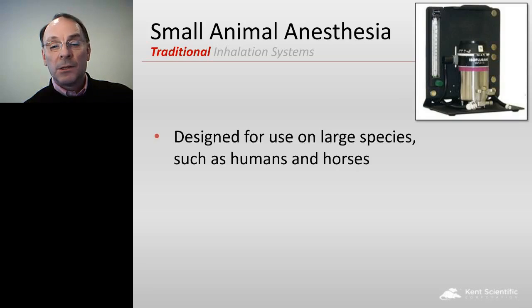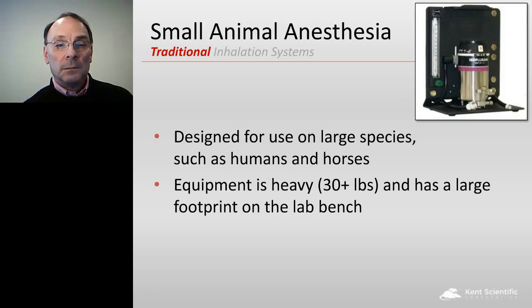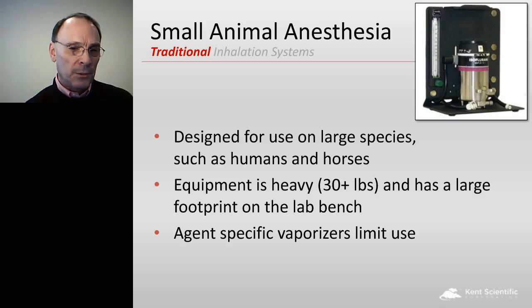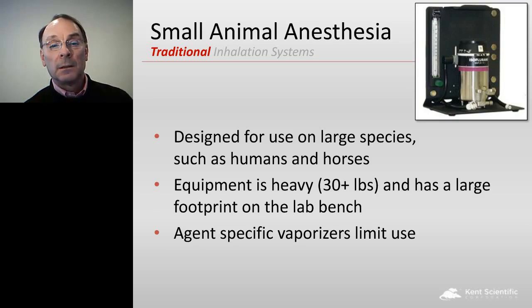Traditional small animal anesthesia systems typically are designed for humans and larger species, such as horses. The same vaporizer that people are using on a mouse can be used on a horse or a larger animal. It's all mechanical. The standard vaporizer, besides requiring large airflows, typically weighs, as it says here, 35 pounds or 30 pounds, and has a large footprint on the lab bench. Even a tabletop stand will have a fairly large footprint. The weight is caused by a heat sink that's built into the vaporizer, because as the anesthetic evaporates, it draws energy from the environment, being the vaporizer, which drops the temperature of the vaporizer, so it needs a big heat sink of solid metal to try to control that temperature drop.